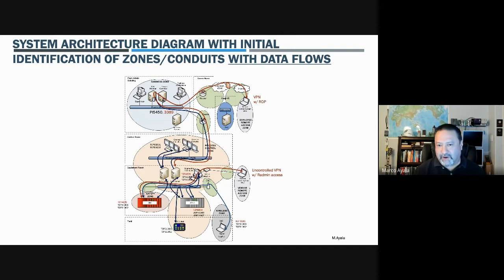Finding out that you have this type of communication where you shouldn't is very important. Another one in this drawing that I try to capture and show is that uncontrolled VPN that's sitting out down further to the right in the equipment room zone. It shows coming in and going out from vendor remote access zone. You can see it pivots in through the engineering workstation through either a dial-up or cell modem, and it comes in and can actually talk to either the basic process controller or the safety zone. In this instance, this is actually showing it's communicating through the engineering station utilizing the engineering station to communicate to the safety instrumented system or safety controller. Would you have known that without actually looking at data flows and pulling P-caps and using mirrored ports? Probably not. There's many companies out there that have that sensor type technology, threat detection type technology that can sit as a bump in the wire or span off a port or mirrored port to give you visibility.